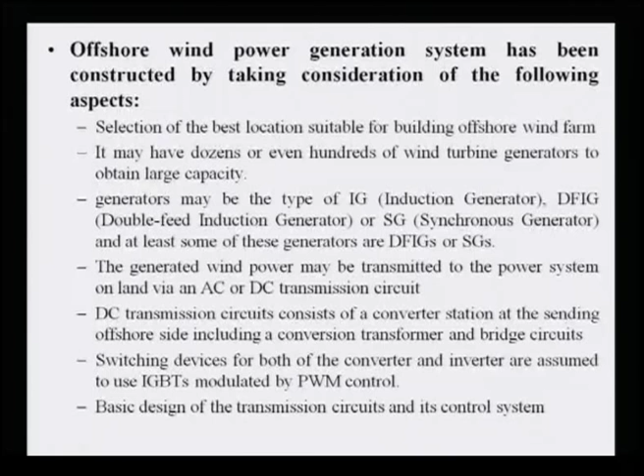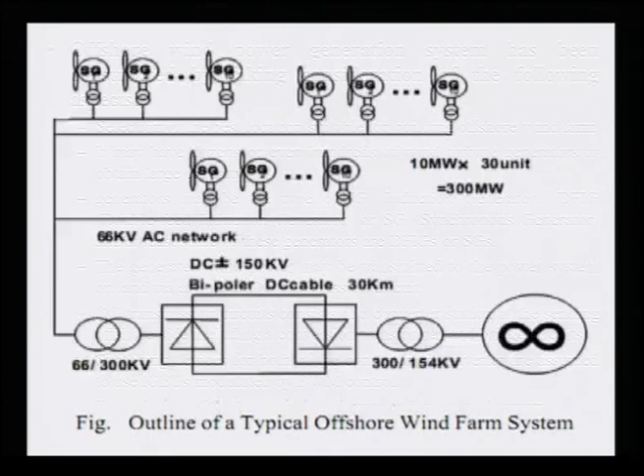In this case, if HVDC Light is put along with the conventional system, the whole operation of the power system is improved significantly. So, a single phase to ground fault is set at the AC bus of the HVDC 1 converter. Suppose the fault is applied at point 4 while the system is operating steadily, and the fault is sustained for 5 cycles, that is 0.1 second. We can compare with and without HVDC Light. If this fault occurs without HVDC Light, the system becomes unstable. If you put HVDC Light here, the system becomes stable.